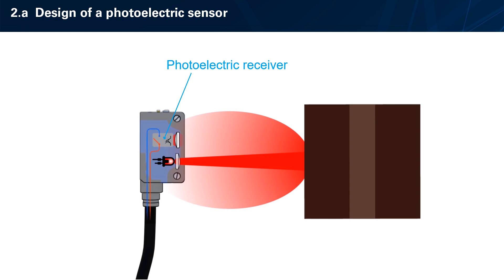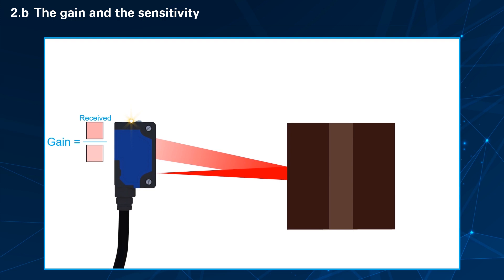As the light intensity at the receiver increases, the output of the sensor changes state. It behaves like an electrical contact. The gain is the ratio between the received light energy and the necessary light energy to switch the product on. When the quantity of light is not enough, there is no detection.